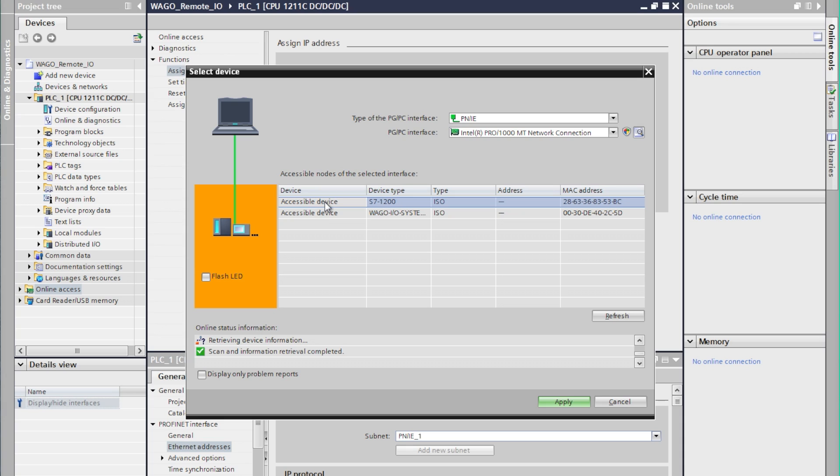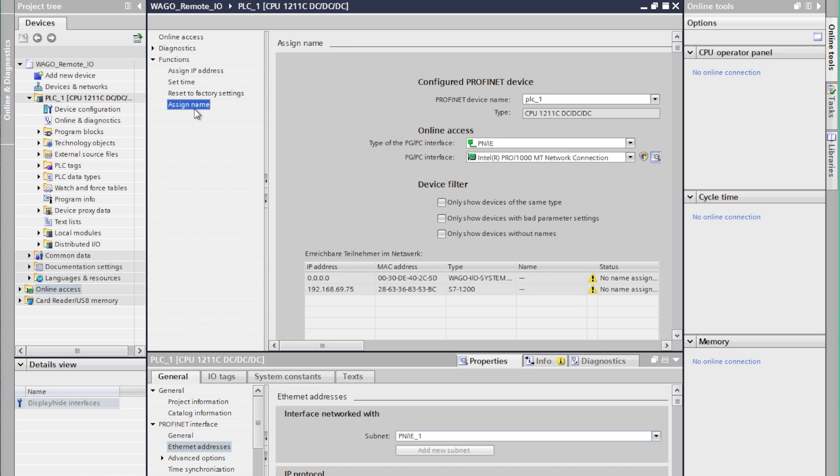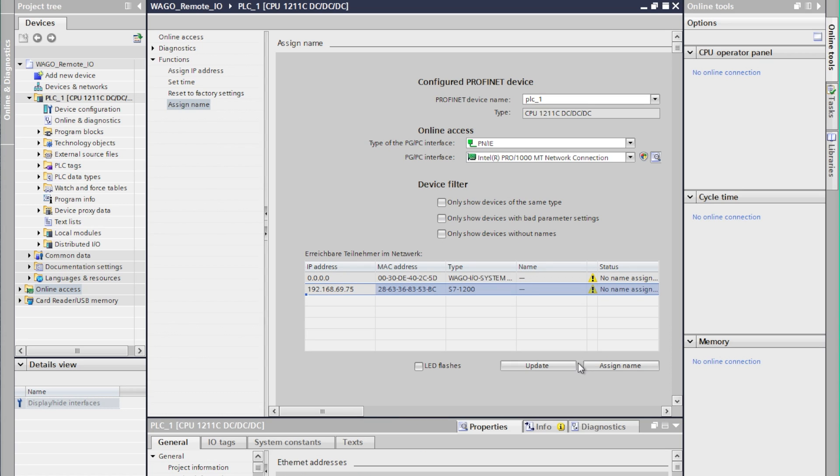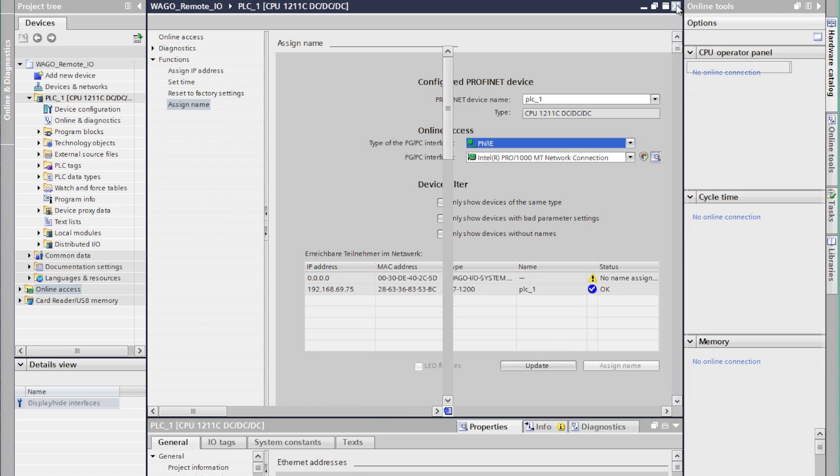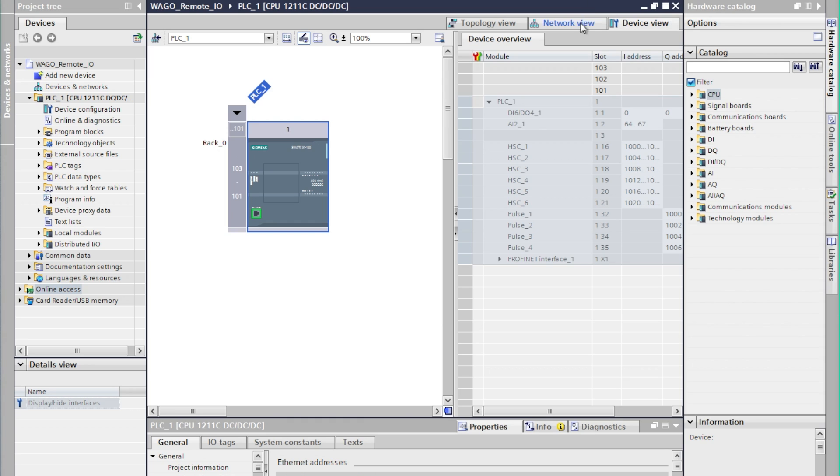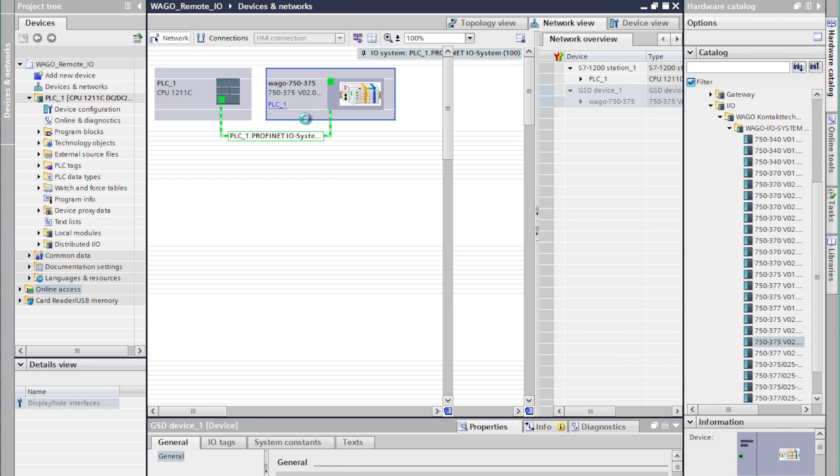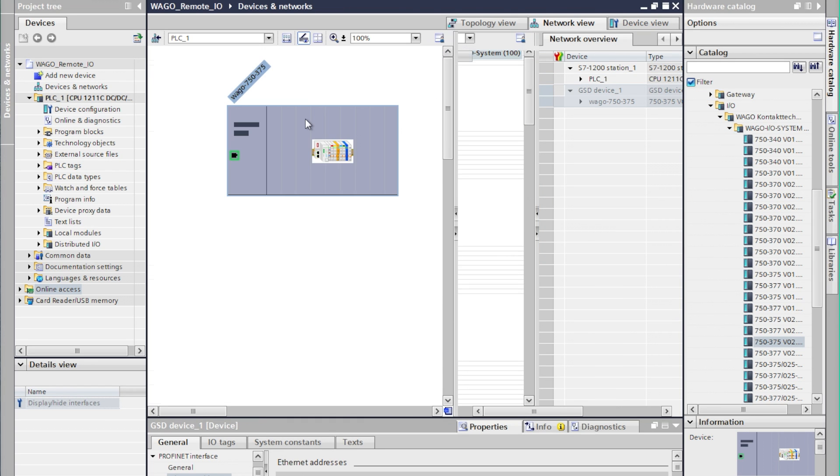We see our S7-1200 there and we will go ahead and apply that to this. Now by clicking assign IP address the IP address that we assigned in the properties tab will be written to the controller. PROFINET is based on a naming system so we'll also need to assign a name. If you go to assign name it will also do a search and we can select the same device and assign it.